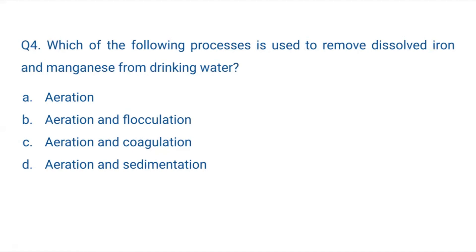Question 4: Which of the following processes is used to remove dissolved iron and manganese from drinking water? The correct answer is D — aeration and sedimentation. When you aerate the water, it oxidizes the iron and manganese present in it. The oxides are heavier, they settle down at the bottom during sedimentation, and then the clear water is removed from the top.